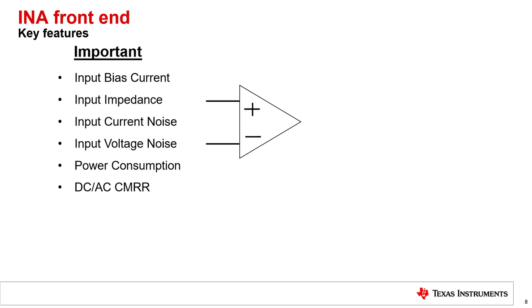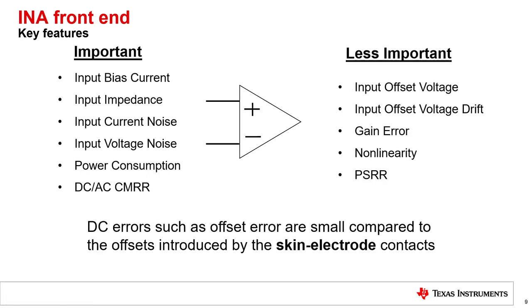Not important: generally DC specifications like offset, gain error, and non-linearity do not matter because the offset of the skin electrode contacts are typically much larger than errors introduced by an INA. In addition, drift is not usually a concern because the temperature range of the application is typically narrow. Finally, PSRR is generally not a concern if power supply design is done properly with adequate placement of power supply sources and decoupling capacitors.